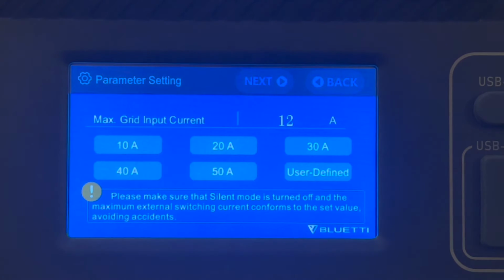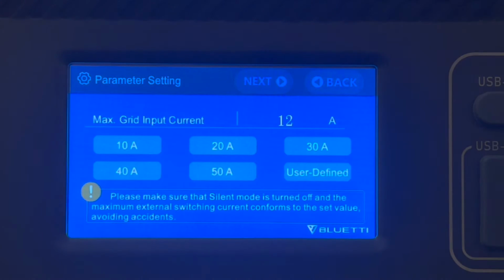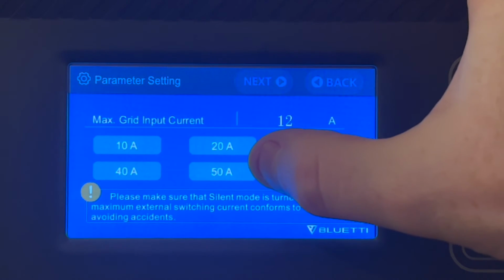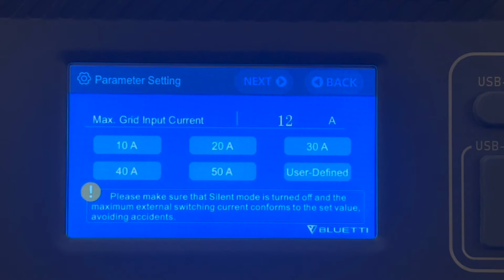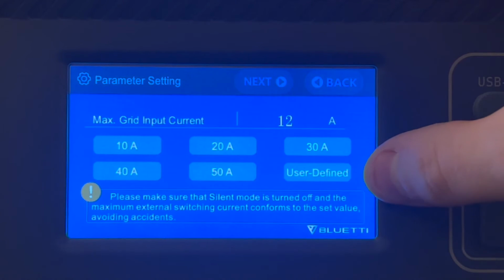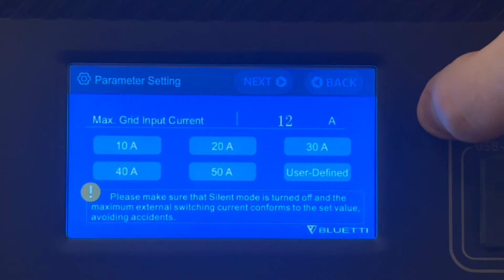Okay, so here's the more advanced version of the menu. So you can set the grid input all the way up to 50 amps. Now that requires a cable that can support that much. If you were to set it to 50 amps and you use the cable that comes with the device, you're simply going to blow your circuit breakers. Right? If you wire things up badly, you could have more problems, but mostly you're going to blow circuit breakers if you have this issue. The user-defined button inside underneath the password menu, you can set it all the way up to 50.